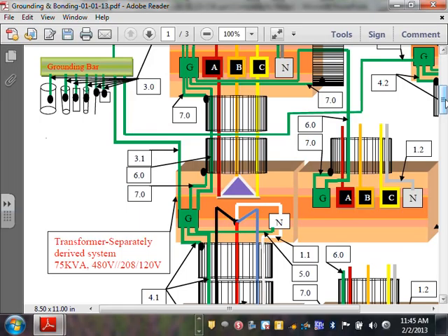But you don't have to go all the way back, it's very clear. You can pick up that system some other place with an approved system like building steel, but a water pipe is not. Another thing, one second, if you go to the other end of the building and you put a transformer, you drive a ground rod there and you tie to it. Same building. I have a separately derived system. I went to the service in the east. In the west, 200 feet away, I took a transformer, separately derived system. I drove a ground rod in that area, tied to it. You still need to tie that, and it's just a wood building. No steel, nothing. You still have to tie the two grounding electrode systems together. So they end up forcing you to have a number 6 tying the two grounding electrode systems.